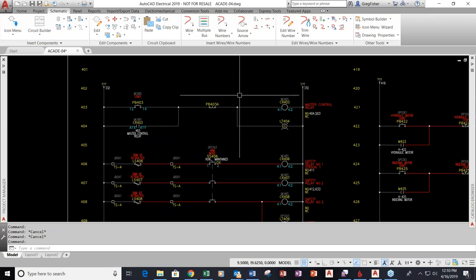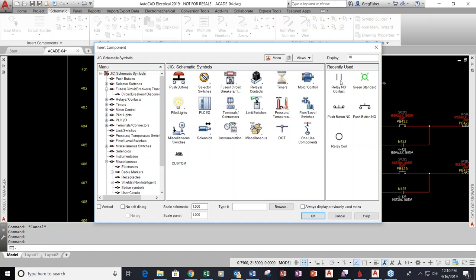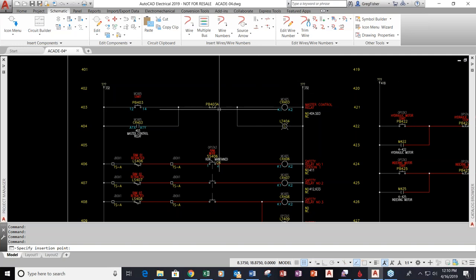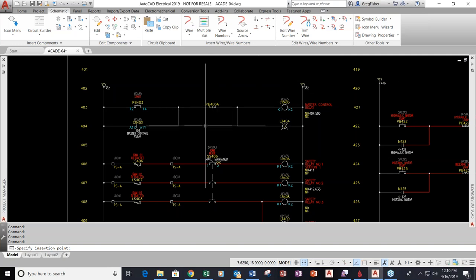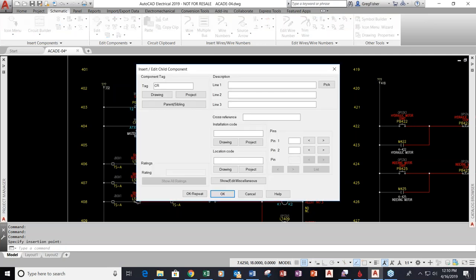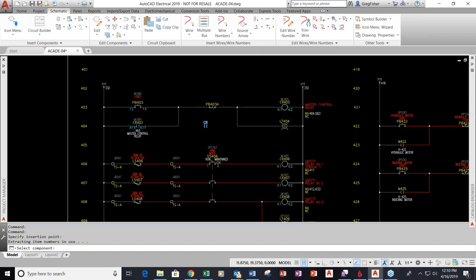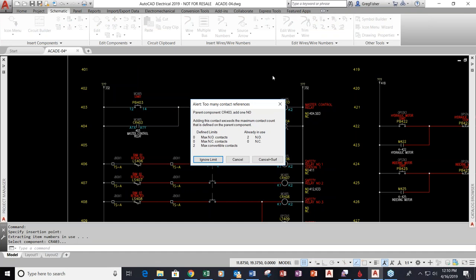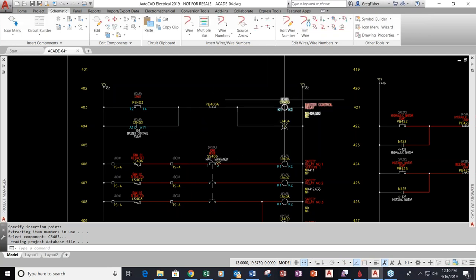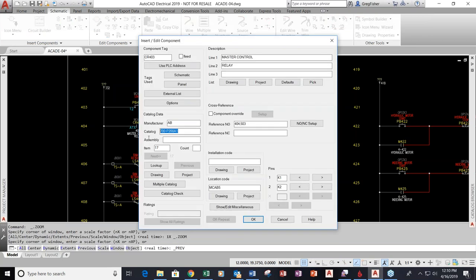Another thing I can do is this error checking. The part number established for that parent symbol was only good for two contacts. If I try to assign a third one — let's say I forgot how many contacts I had already used — this is the error checking built into AutoCAD Electrical that we won't find in regular AutoCAD. It knows that part number is only good for two contacts. Normally what I would do is cancel, go to my parent symbol, and edit the part number so it reflects a four-contact relay instead of just a two.